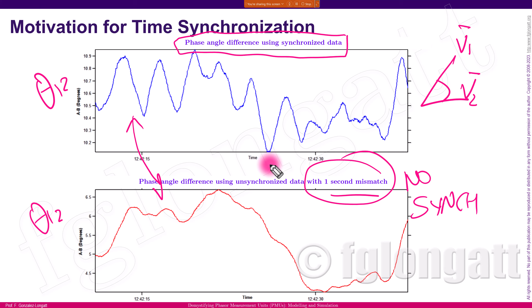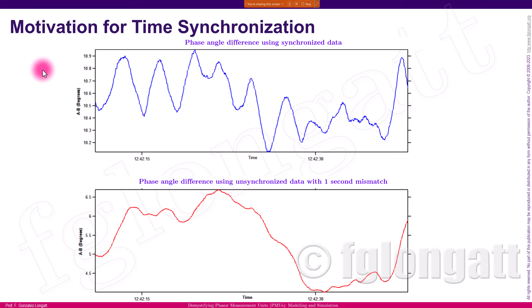I believe you can all see that having a desynchronized signal creates a different phase angle, and that phase angle defines the power flow between the two points. So we need synchronization to produce the best, real result for the phase angle. Now the question is, how do we achieve synchronization?